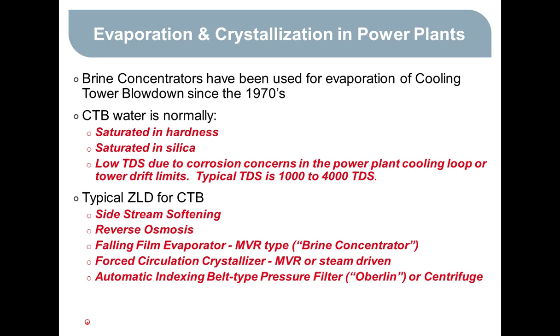And that evaporator can concentrate, as we said in the earlier part of the presentation, up to 20 to 25%. And then that 20 to 25% brine that comes out of the evaporator goes to a forced circulation crystallizer, which may also be an MVR-driven or a steam-driven type unit. And then finally, the final solid separation is done a lot of times with what's called an Oberlin filter. I'll talk later about what that is specifically, but it's an automatic indexing pressure filter, or sometimes the centrifuge is used to separate out the solids.